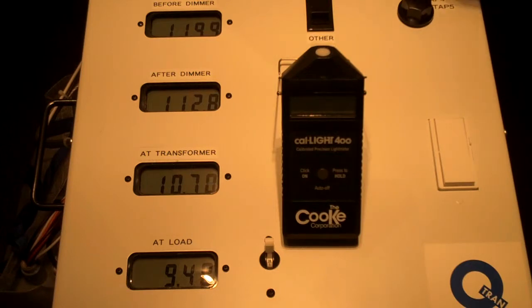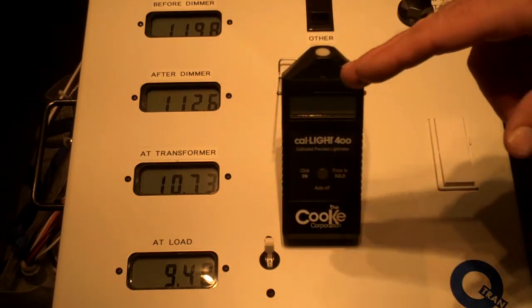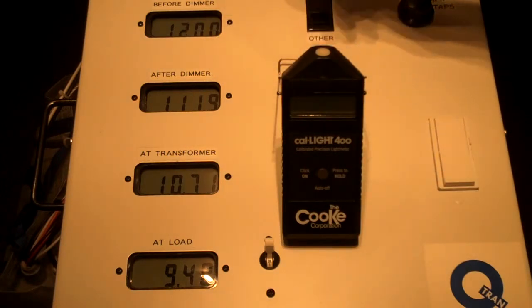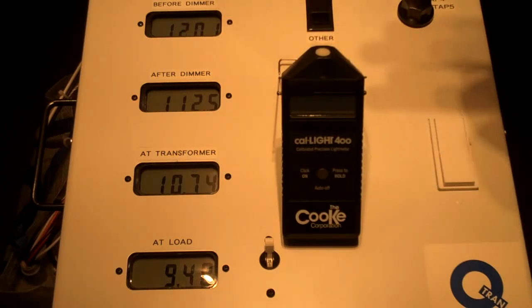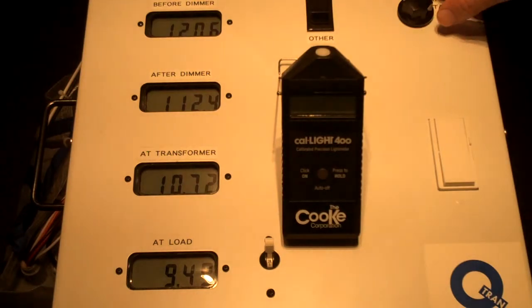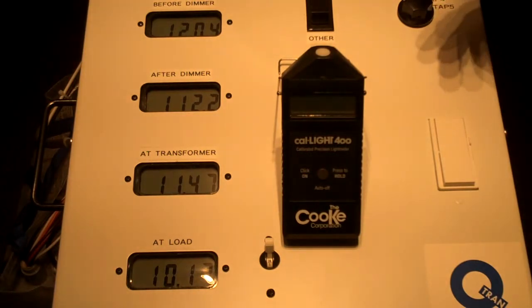So on our 12 volt tap, which is tap 2 here, you will notice that we're putting out about the same voltage. We're about 113 after the dimmer. We're 10.7 coming out of the transformer. We're about 9.5 out at the load. But with our multiple taps, when a contractor gets a reading like that, he merely bumps up the voltage 1 volt at a time till he gets to the right voltage out here at the load.